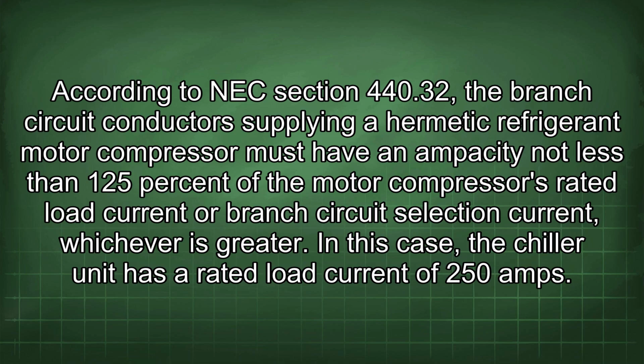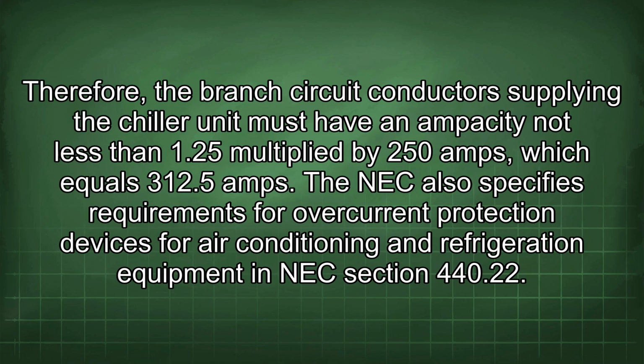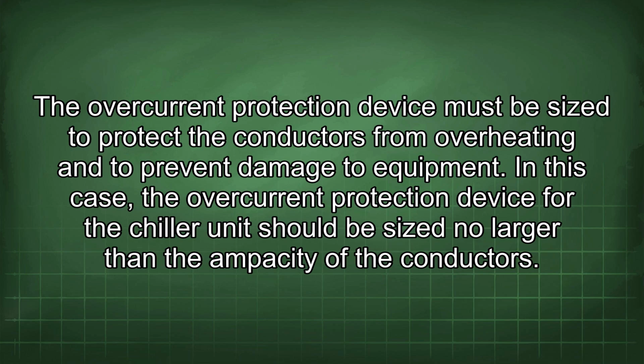In this case, the chiller unit has a rated load current of 250 amps. Therefore, the branch circuit conductors supplying the chiller unit must have an ampacity not less than 1.25 multiplied by 250 amps, which equals 312.5 amps. The NEC also specifies requirements for overcurrent protection devices for air conditioning and refrigeration equipment in NEC Section 440.22. The overcurrent protection device must be sized to protect the conductors from overheating and to prevent damage to equipment. In this case, the overcurrent protection device for the chiller unit should be sized no larger than the ampacity of the conductors.